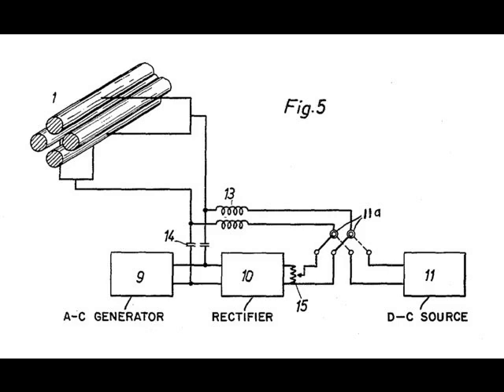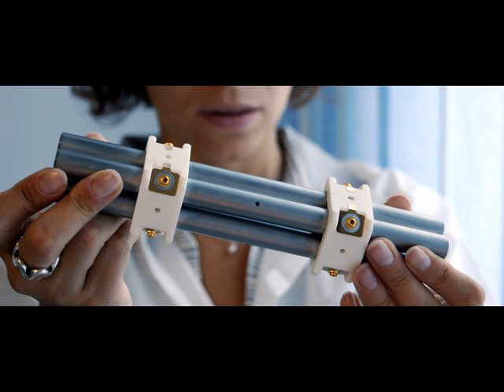The quadrupole consists of four parallel metal rods. Each opposing rod pair is connected together electrically, and a radiofrequency (RF) voltage is applied between one pair of rods and the other. A direct current voltage is then superimposed on the RF voltage. Ions travel down the quadrupole between the rods, and only ions of a certain mass-to-charge (m/z) ratio will reach the detector for a given ratio of voltages.